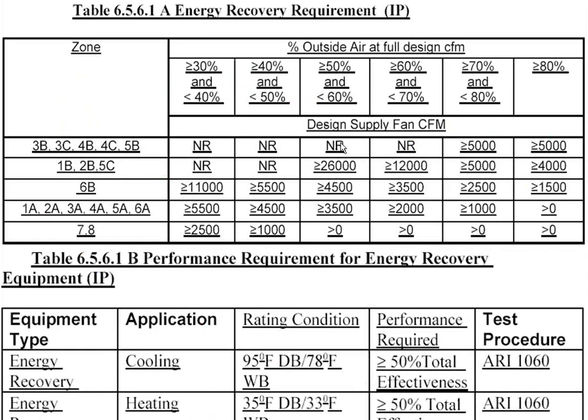So if we look at the energy recovery requirement, because we're not only using, here we've got the zones on the left, we've got the western regions up here, and then here in Illinois we're 5A with the other moist eastern climates here. So we've got it broken up by zone, also east and west, temperature and humidity zones, and also by percentage of outside air. So let's look at 5A, which is Illinois. If we have a 5,500 CFM design in our system, and between 30 and 40% of that is outside air, then we're required to use an energy recovery ventilator.